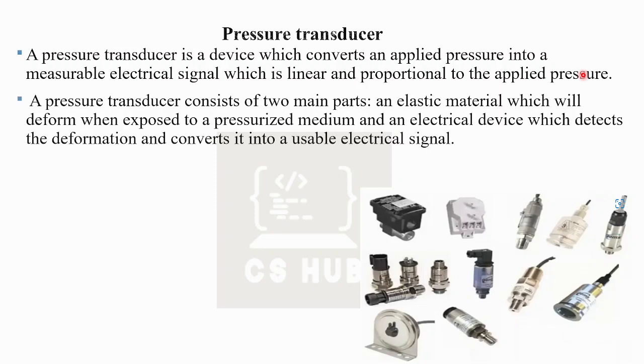The pressure transducer consists of two main parts: first, an elastic material which will deform when exposed to a pressurized medium, and second, an electrical device which detects the deformation and converts it into a usable electrical signal. We use the strain gauge.